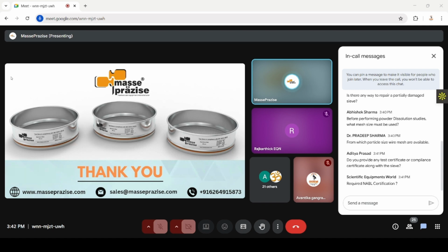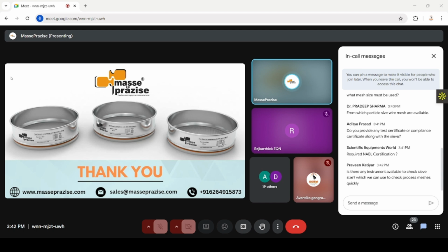Is there a way to repair a partially damaged sieve? No, it has to be replaced. There are two options. There are test sieve makers that have a single uniform sieve that may not be repaired, and there are some manufacturers that have a separate ring that can be repaired. So the frame can be saved and only the mesh can be repaired. It depends on the manufacturer and what type of sieve they are manufacturing.